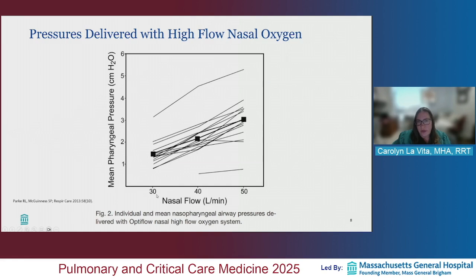The general rule of thumb is for every 10 liters a minute of high flow nasal cannula flow that you have, you're probably generating about 1 centimeter of water of CPAP. Now that is under the most optimal conditions, which includes a very snug fit of the prongs within the nare. It also includes the patient's mouth to be closed. If the mouth is open, a lot of this pressure is leaked out, or it's not recognized because exhalation occurs through the mouth instead of through the nose, where the back pressure is developed from that high flow.